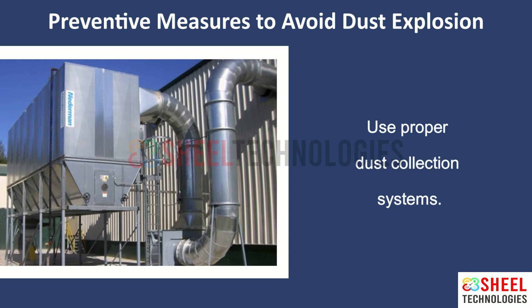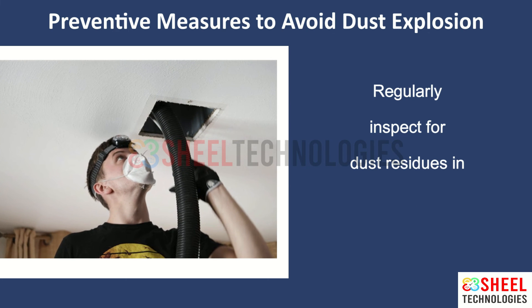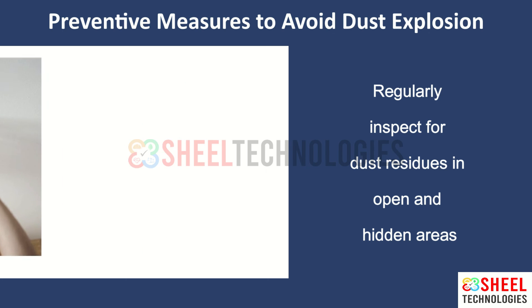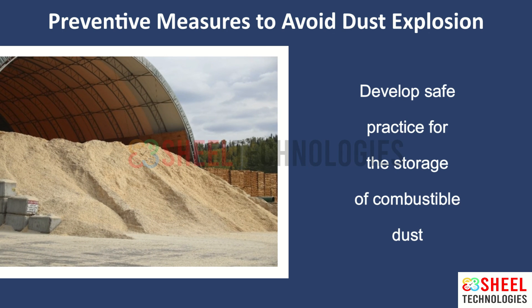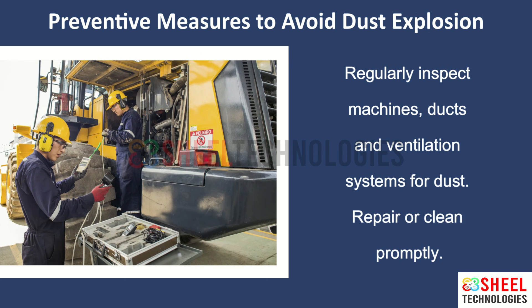Use proper dust collection systems. Regularly inspect for dust residues in open and hidden areas. Develop safe practices for the storage of combustible dust. Regularly inspect machines, ducts, and ventilation systems for dust, and repair or clean promptly.